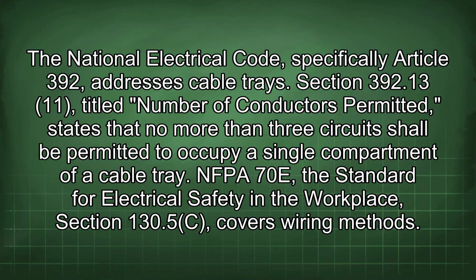The National Electrical Code, specifically Article 392, addresses cable trays. Section 392.13.11, titled Number of Conductors Permitted, states that no more than 3 circuits shall be permitted to occupy a single compartment of a cable tray.